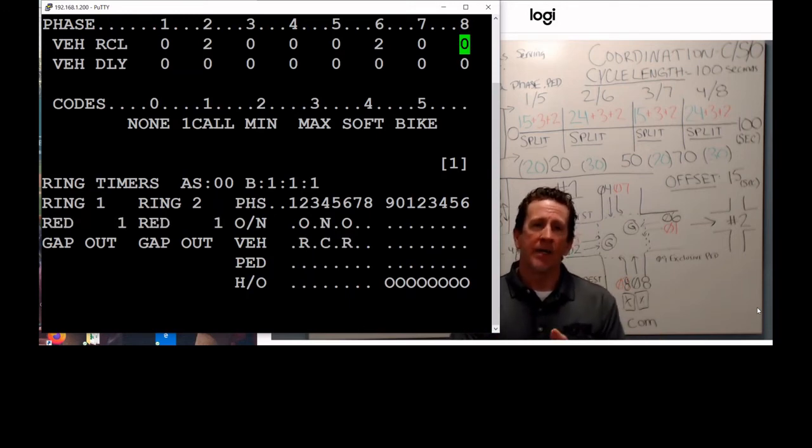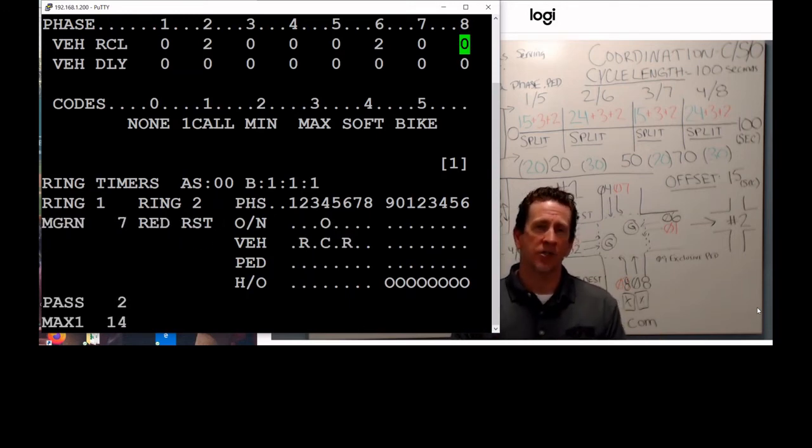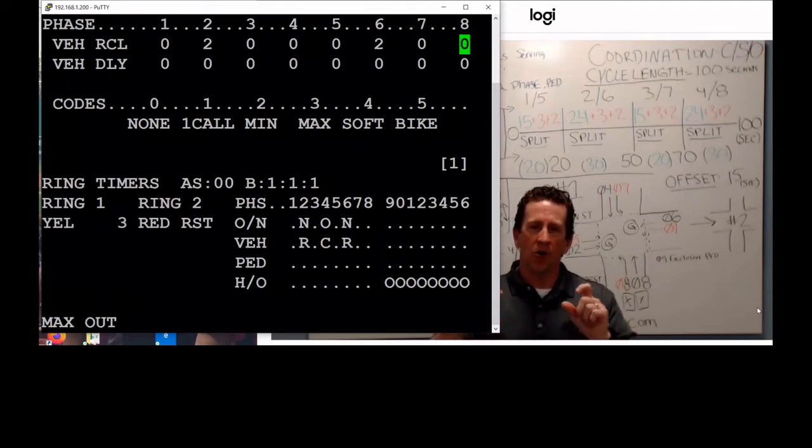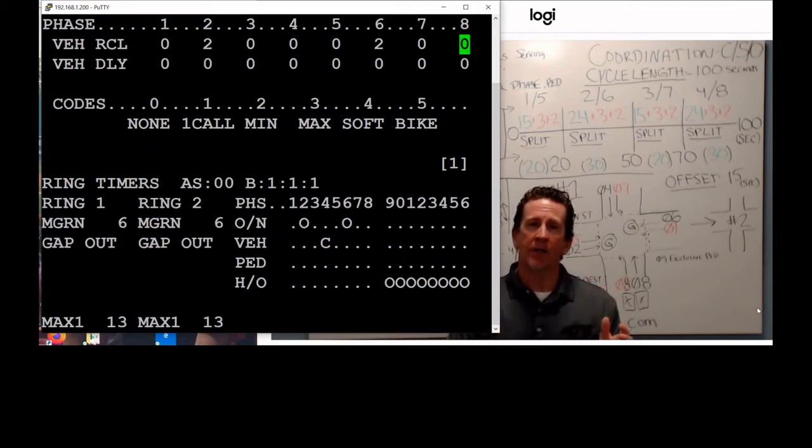In about the mid 90s, we started transitioning over to TS2. And what TS2 did was it introduced the SDLC bus, the synchronous data bus. And instead of having all that wiring on the back panel, we now take all the gray cables, they're usually gray, sometimes green. We plug the controller, the MMU, and the BIUs. I should have brought one with me, I don't have one.